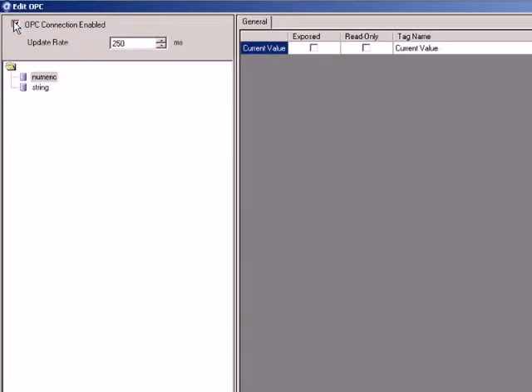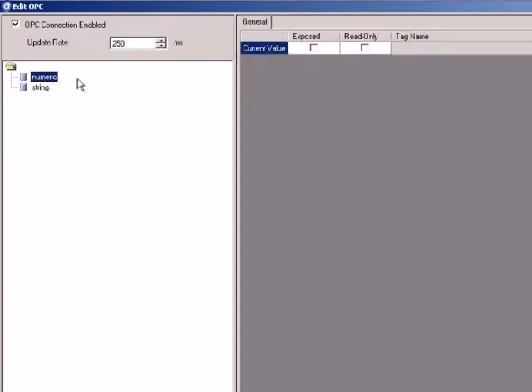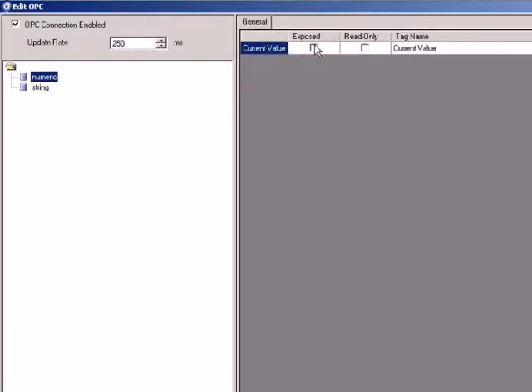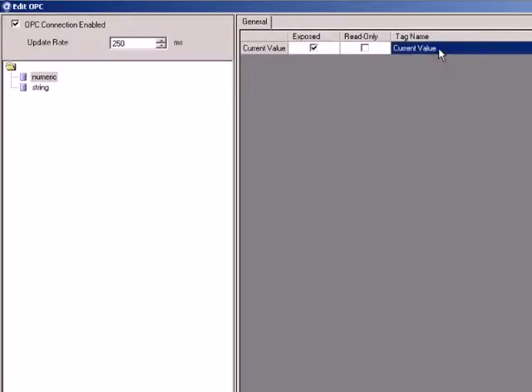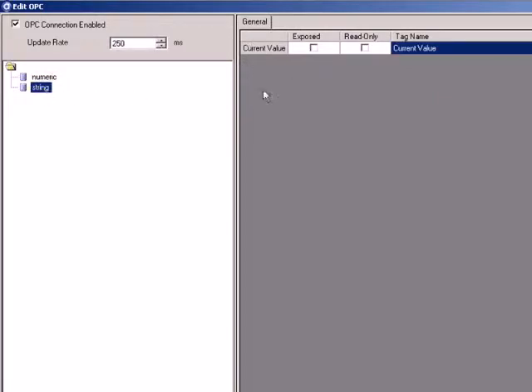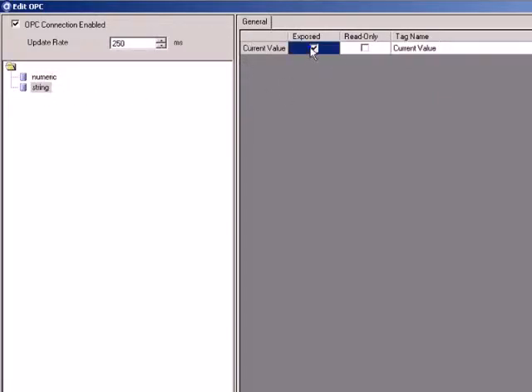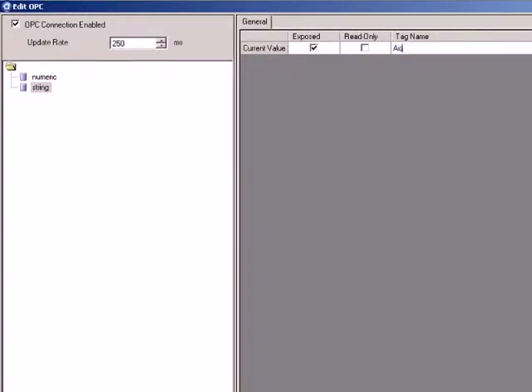Make sure that the OPC connection is enabled and set the update rate to 250 milliseconds. Double-click on Numeric and check the exposed checkbox. The tag name is set to Current Value. Since Current Value is a very generic tag name, let's edit the field. We can call it ACE Numeric. Double-click on String and export the variable. Modify the tag name to ACE String.